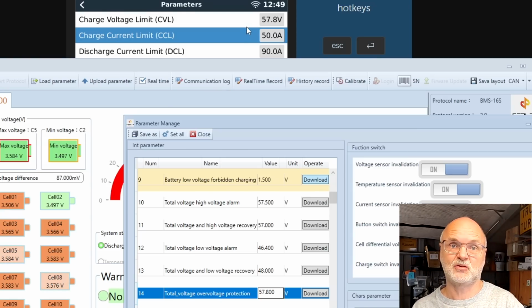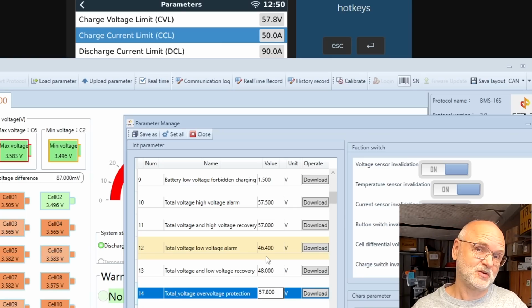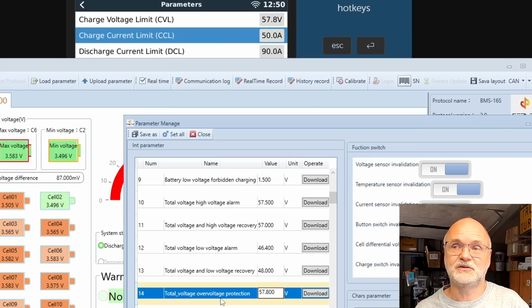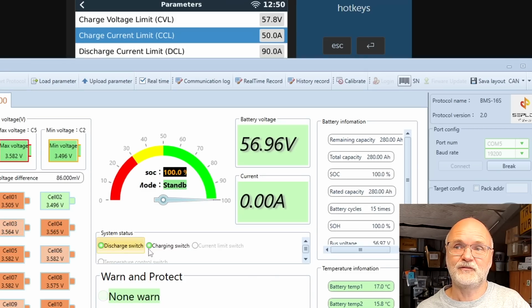So it tells the solar charge controller, charge now to 57.8. This is a one-to-one setting and parameter. You would charge your battery to 57.8 volts, and then the over voltage protection would kick in, which I never liked with the Seplos BMSs, because this turns off your charge MOSFETs. It sets your charge current limit to 0 amps because you are in a protection state with your BMS.